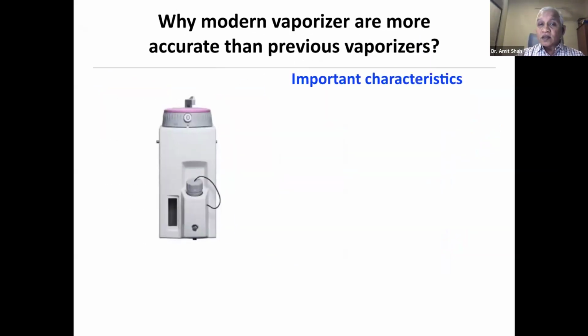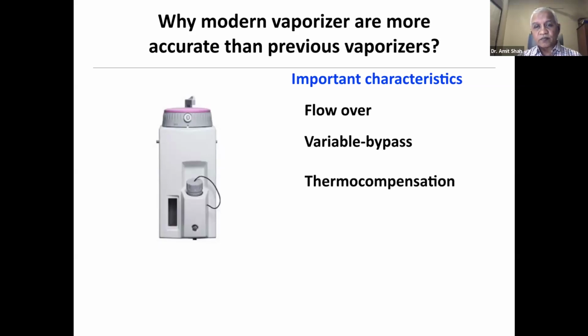For the modern vaporizer, there are some very important characteristics which all postgraduate residents should remember. I'll explain what those characteristics are and how it works. So they are flow over vaporizers. Basically, the carrier gas passes over the liquid, and then there is an open surface where a lot of vapor is formed, and it takes that vapor with it. It is a variable bypass. That means some gas passes out without going through the chamber. Some gas will pass through the chamber and take the inhalation anesthetic.